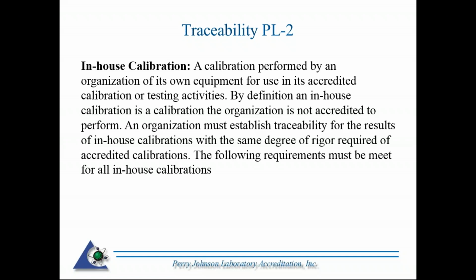So things like the procedure, the personnel, even the traceability, you have to have the appropriate equipment and the environment, everything that an accredited thermometer calibrator would need to have to be accredited. So in-house calibrations or internal calibrations are defined there in front of you, and we go into some detail in PL2. Really the only difference between an in-house calibration and an accredited calibration is that an in-house calibration is not on the scope of accreditation.